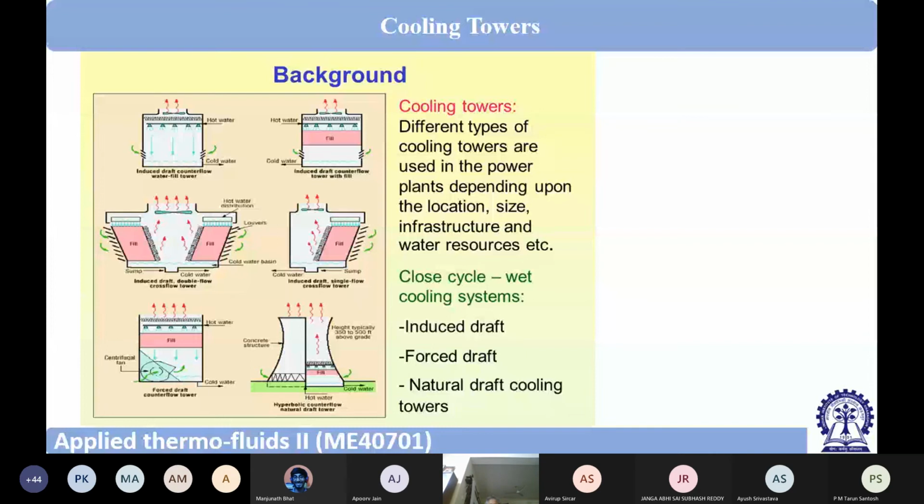Lastly, let me finish by telling that maintenance of the cooling tower is very important. Now, the cooling tower is part of the water circuit, but water is coming in contact with air. And the cooling tower is a very large space. So in the cooling tower, there could be vegetative growth. Vegetative growth means not trees, etc., but algae formation is quite possible. Particularly, where those film type fills are there, algae formation is there. And they will choke the path.